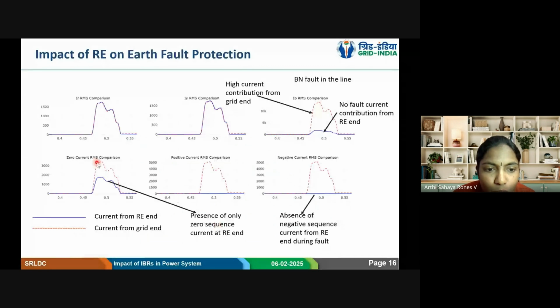So when a fault happened, we can see here IRMS, R phase, Y phase, B phase, all are the same in case of the current from the grid. And the zero sequence, and if we see the current from the RE end, there is no fault contribution at all from the RE end. Only from the grid end we are seeing the fault contribution.